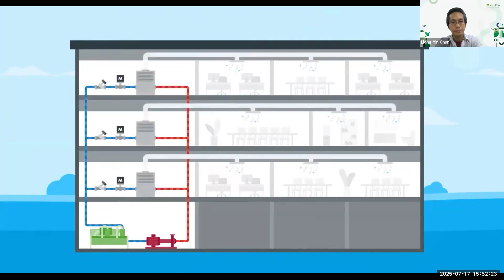There are many considerations when designing a cooling system for commercial buildings. To cool a building, existing chilled water systems generally use large centralized pumps and chillers in the mechanical room for pushing water around the chilled water loops. Regulating the flow due to the varying cooling needs is traditionally done using balancing and control valves, typically located close to the terminal units. But even efficient valves consume unnecessary energy due to pressure losses.